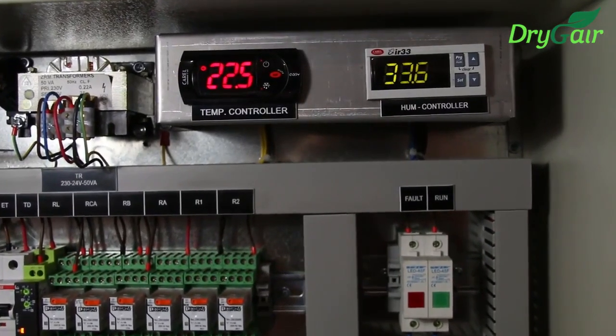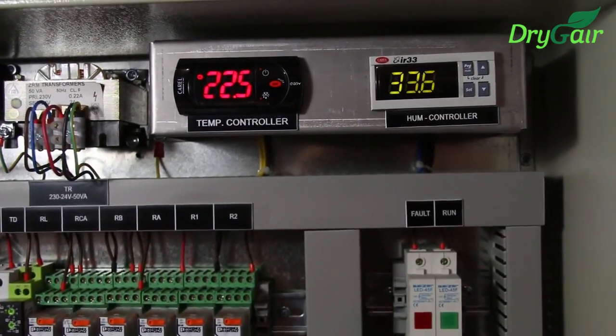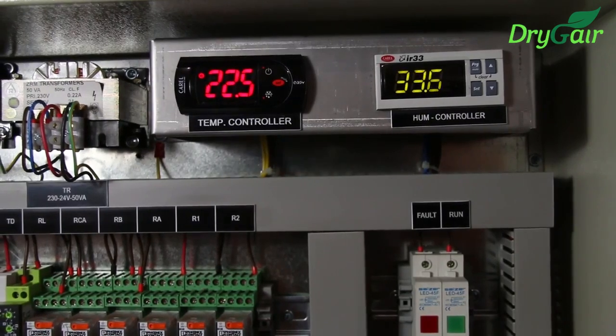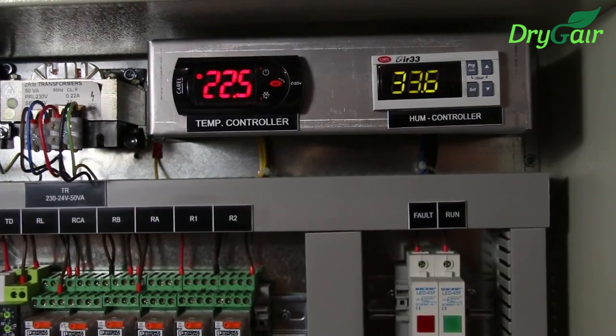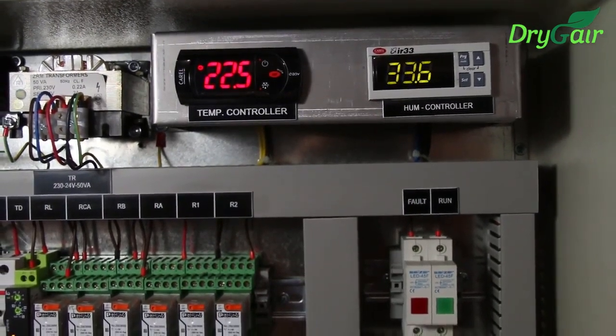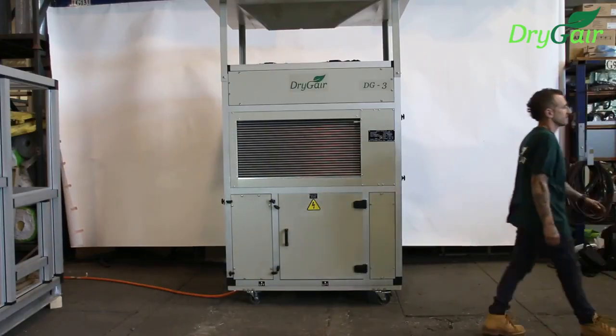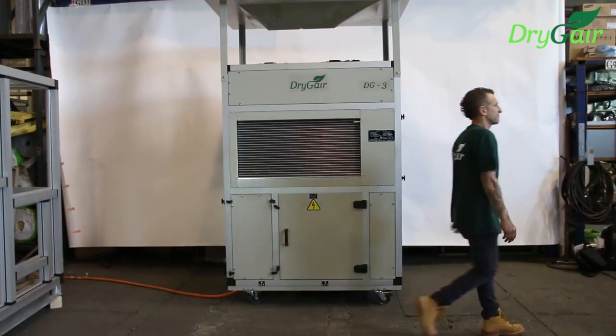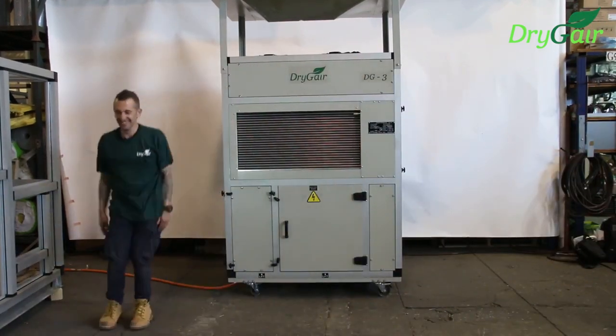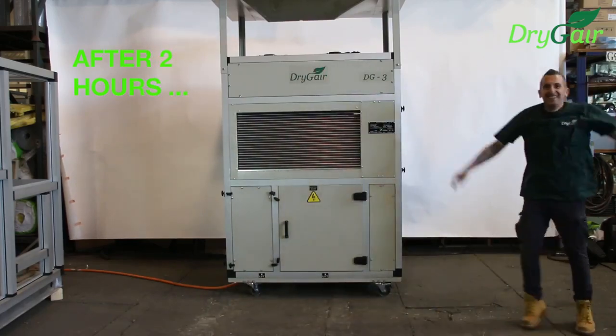The temperature controller is on the left. It comes preset by the manufacturer and shouldn't be adjusted. It will show you the temperature according to the unit sensor, which in this case is 22.5 degrees Celsius. Remember that when you first install the DryGair unit, you must wait 2 hours before you can begin to operate. 2 hours have passed, and now we are ready to begin.